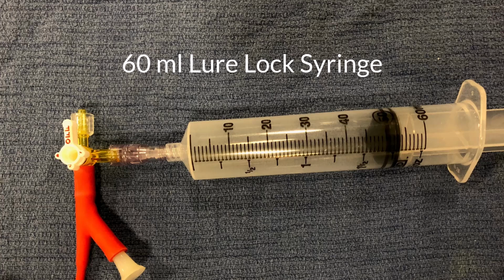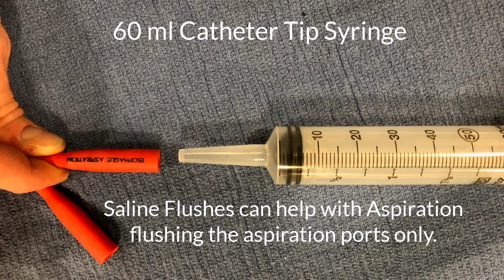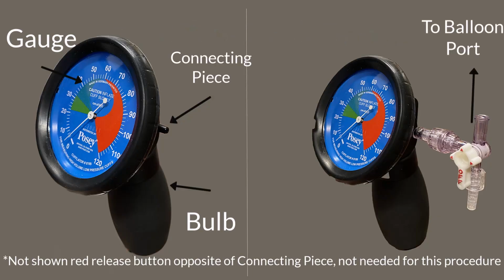For simplicity, you can use the 60 mL catheter tip syringe directly into the port without the three-way stopcock, but the stopcock will be needed for pressure testing. The 60 mL catheter tip syringe is used to aspirate or inject air into the aspiration ports. To connect the manometer to the luer lock, press firmly, no twist needed, and you should see the needle move immediately with a pressure reading in centimeters of water.